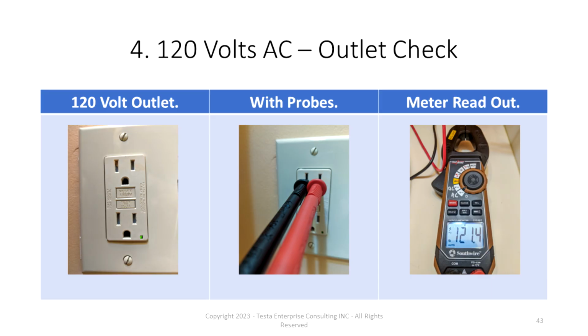You can use a polarity checker to tell you if it's wired correctly. You can also put the red probe in the smaller slot and the black one in the ground — it should still show 120 volts or somewhere near it. If the black probe is in the big slot on the left, which is the neutral, it will not show 120 volts. It might still show some voltage, but not anything near 120.